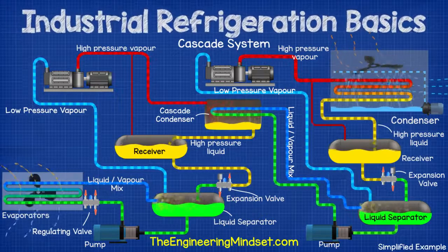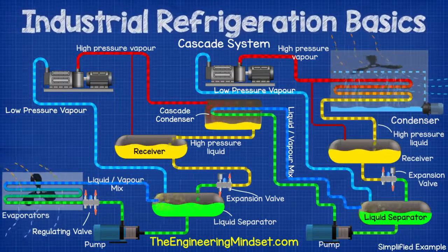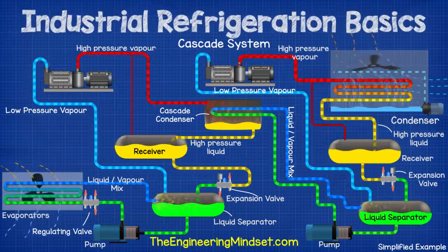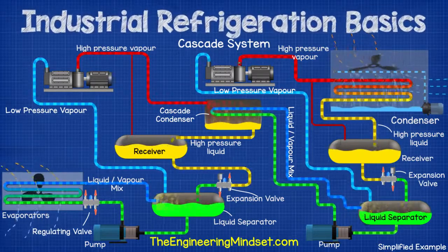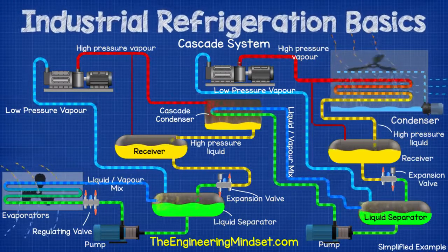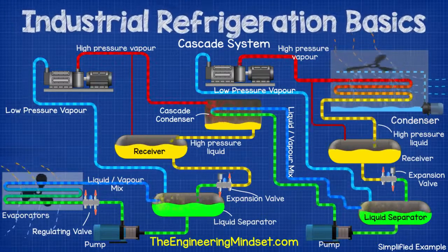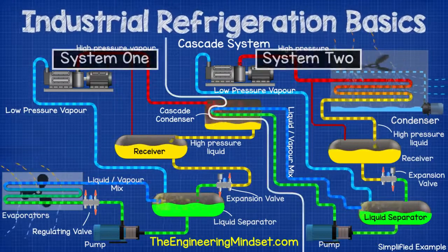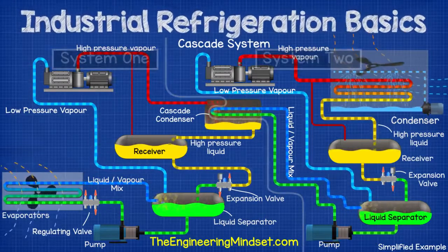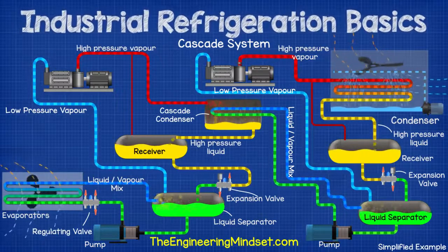It is a little daunting when you first look at this system, but if you've watched this video all the way through without skipping, then you should be able to follow how it works. Just give yourself a moment to trace the pipes and see where everything is flowing. These refrigeration systems usually consist of two or more separate refrigeration circuits, often using different refrigerants to provide a cooling effect. In this system, we have two compressors, except they are both circulating refrigerant around separated circuits — a high temperature circuit and a low temperature circuit.